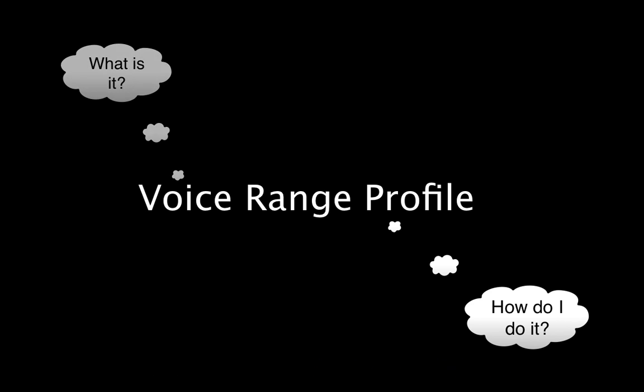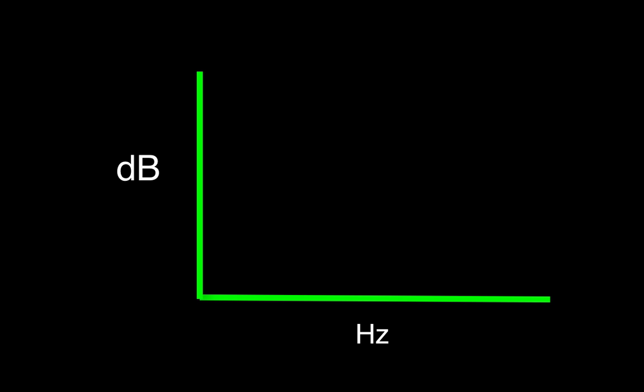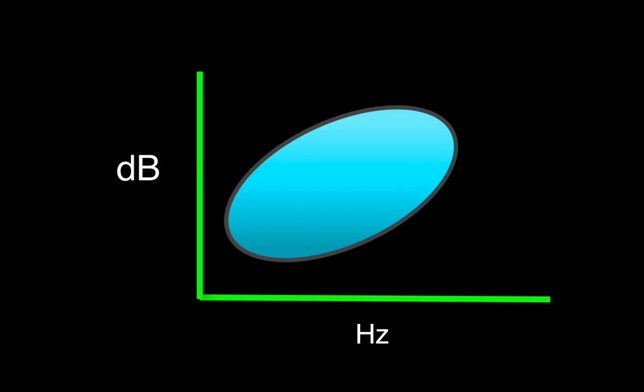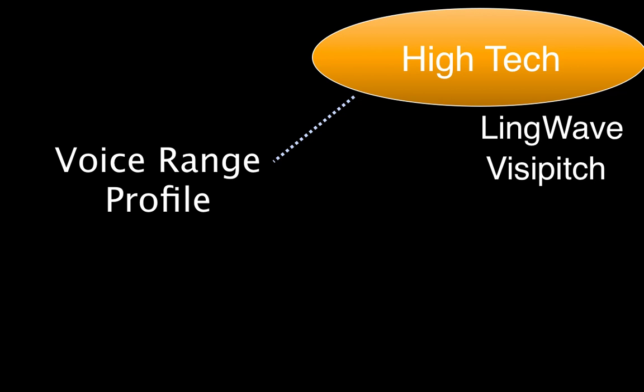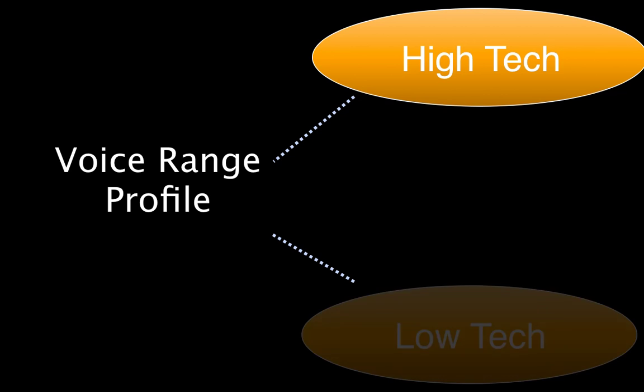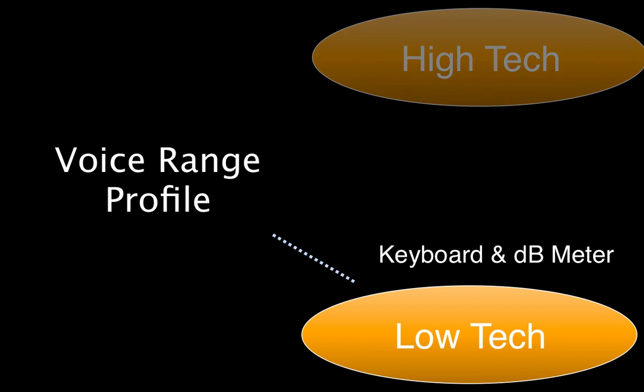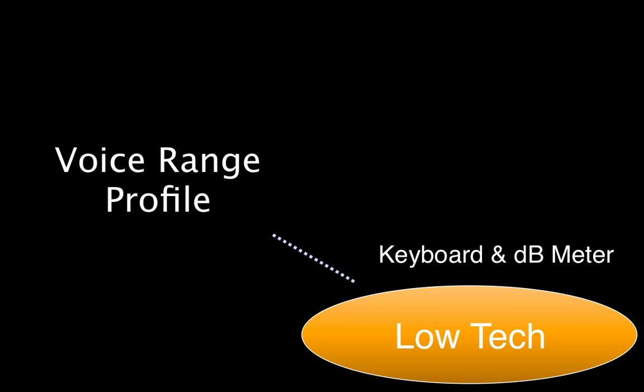Voice Range Profile: what is it, and how do we do it? The Voice Range Profile plots the dynamic range in decibels as a function of the fundamental frequency range. This represents the extreme possibilities of the voice. While these extremes may not be essential for all voice patients, it is an important measurement when considering professional voice users, particularly singers. While there are computerized versions that automate the Voice Range Profile, such as Ling Waves or the KayPENTAX Voice Range Profile, there is also a way to do it using common low-technology instruments, such as a dB meter and a keyboard or frequency tone generator.